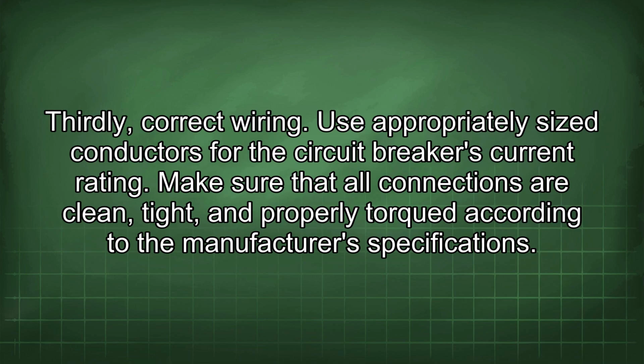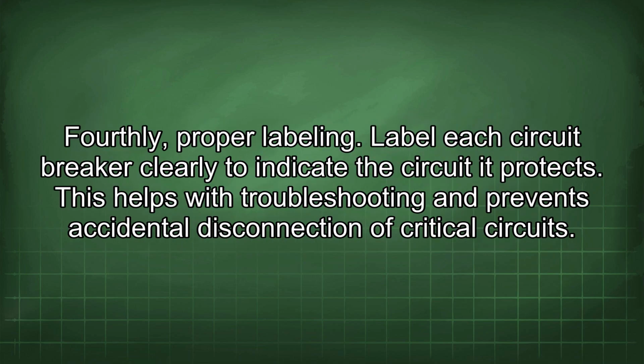Thirdly, correct wiring. Use appropriately sized conductors for the circuit breaker's current rating. Make sure that all connections are clean, tight, and properly torqued according to the manufacturer's specifications. Fourthly, proper labeling. Label each circuit breaker clearly to indicate the circuit it protects. This helps with troubleshooting and prevents accidental disconnection of critical circuits.